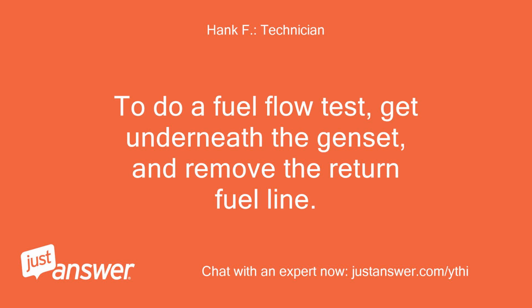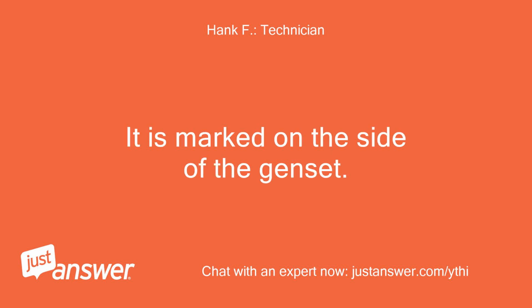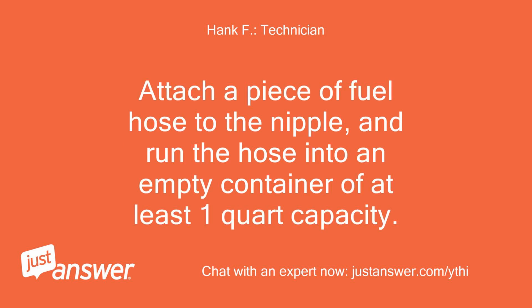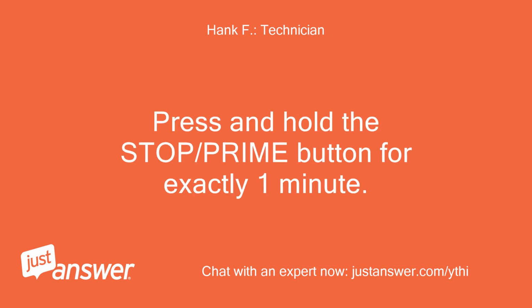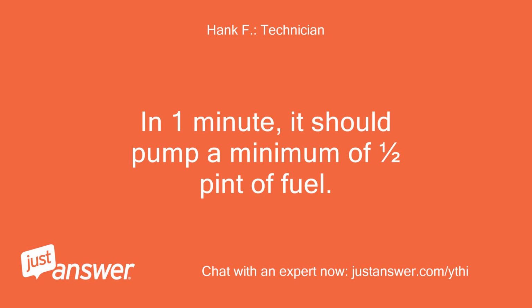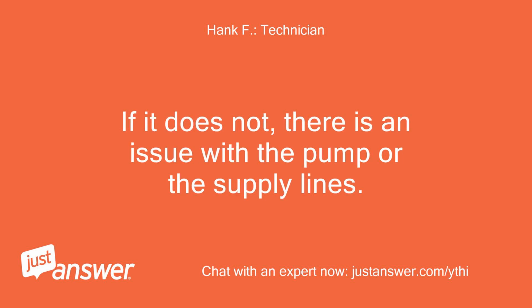To do a fuel flow test, get underneath the genset, and remove the return fuel line. It is marked on the side of the genset. Attach a piece of fuel hose to the nipple, and run the hose into an empty container of at least 1 quart capacity. Press and hold the stop/prime button for exactly 1 minute. In 1 minute, it should pump a minimum of half pint of fuel. If it does not, there is an issue with the pump or the supply lines.